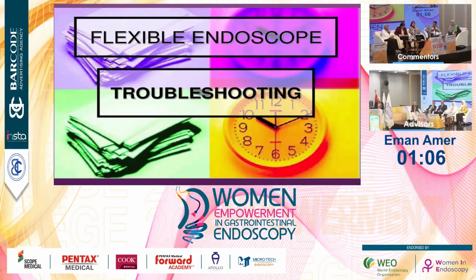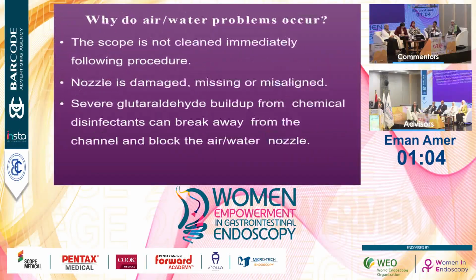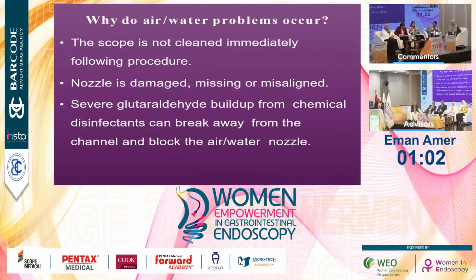So, flexible endoscopy troubleshooting. Why do air and water problems occur? The scope is not cleaned immediately following the procedure, so you must clean it. The nozzle is damaged, missing, or misaligned. Severe glutaraldehyde buildup from chemical disinfectant can break away from the channel and block the air-water nozzle.